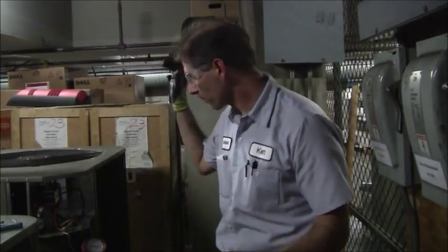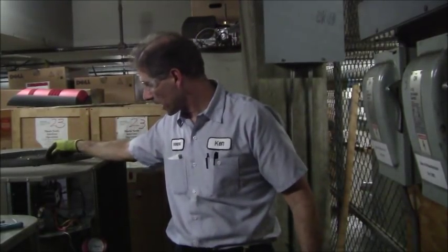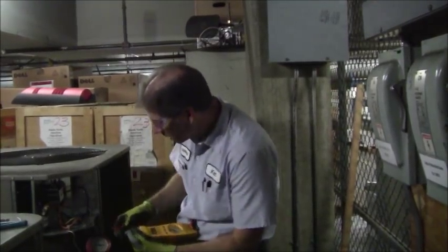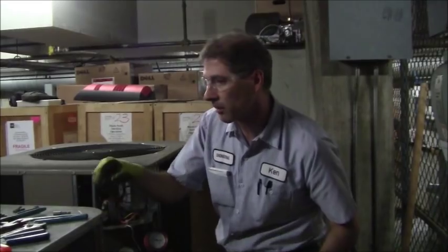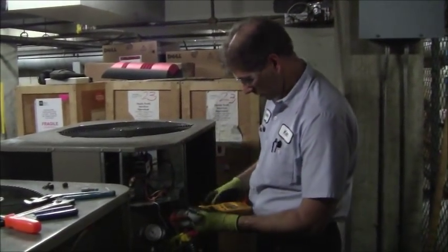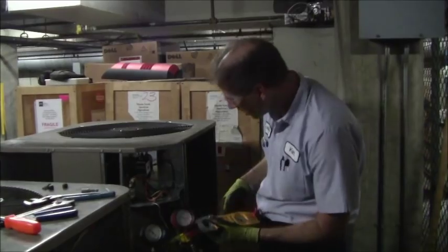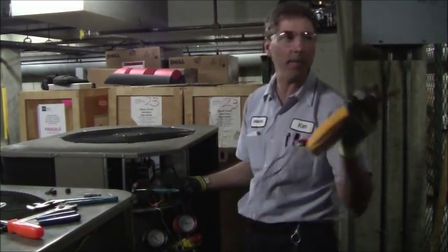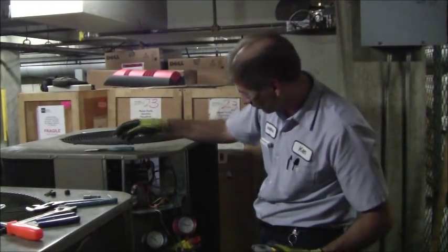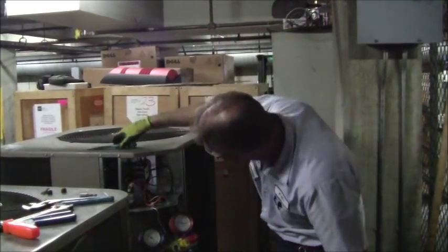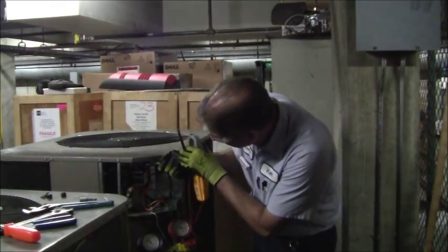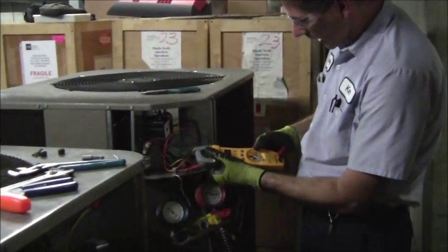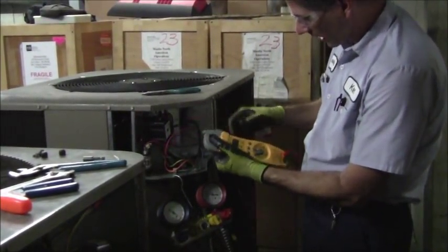What I may have done is I may have shorted the internal overload on the compressor. So what I'll do is let me short out that capacitor again. Do an NCV down here, everything's good. Short out that capacitor since I'm going into the unit after I turned it on. Every time you do the disconnect, you need to short that out. I'm going to lift up one wire going to the condenser fan motor, and then I'm just going to go ahead and do an ohm reading on the 3 phases.